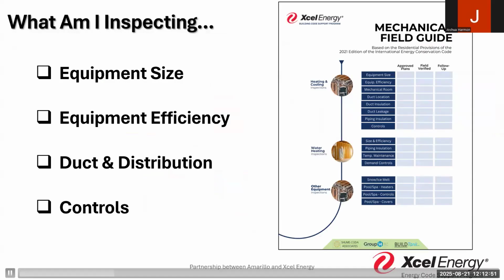I've approved a size, I'm verifying it in the field. I've approved an efficiency level of equipment, I'm expecting to find it. I know there's a duct system that's been designed and laid out to provide certain amounts of air - I'm going to verify that. And then there's going to be a control system, right? We just can't let it run 24/7 if that's not the design.